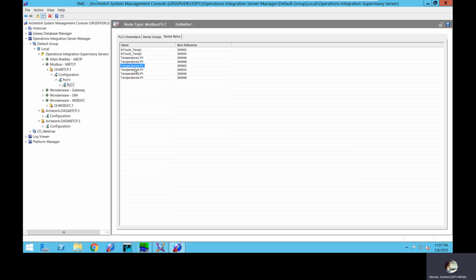Those are the item names that I need to use inside my system. Now, the item names I chose here are the same hierarchical name dot attributes inside my system. Why? Because this is what auto binding will take. It will take the hierarchical name dot the attributes. The attribute is PV. The hierarchical name is only the tag name temperature 1, 2, 3, 4.